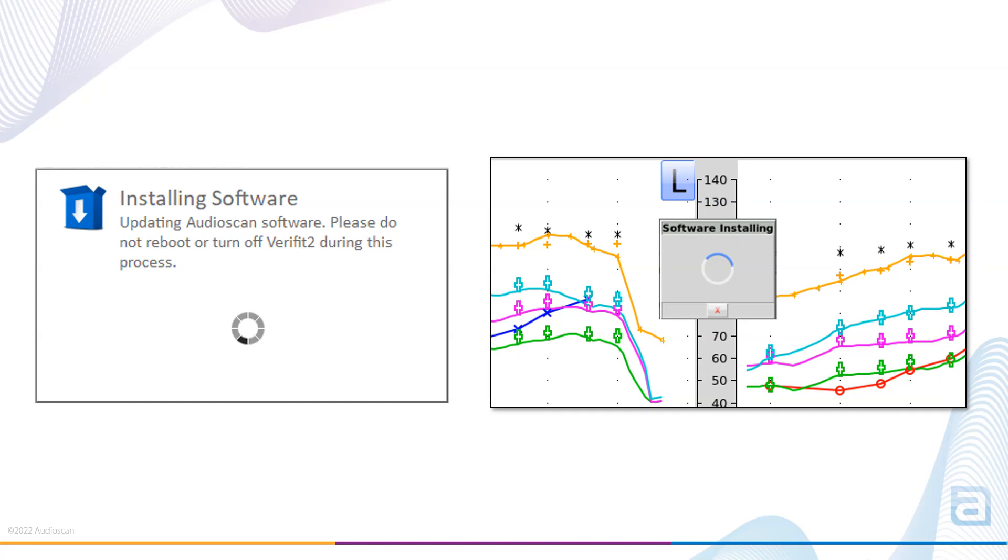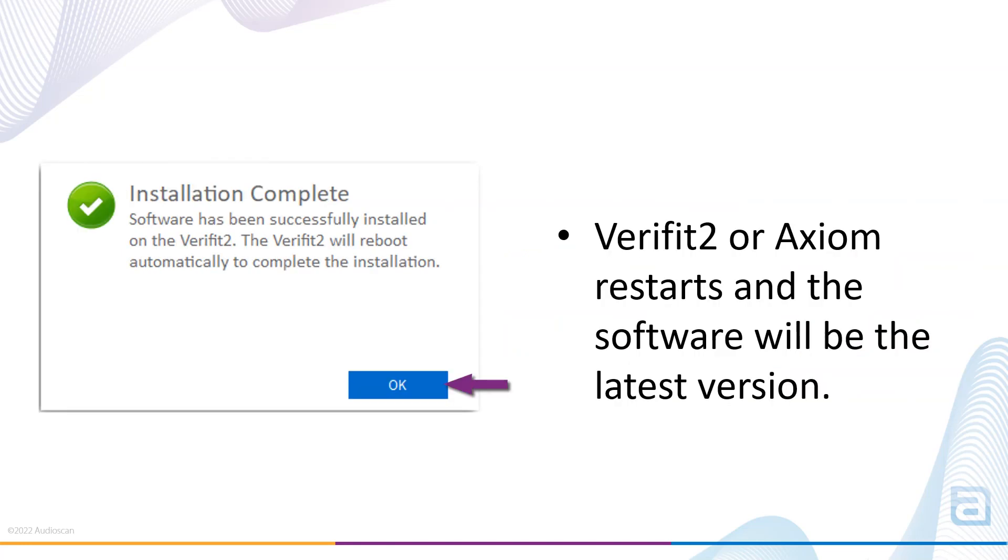If on the off chance you have a network issue or the equipment is turned off during installation and the update only partially completes, we recommend then using the Audioscan update USB stick to install the software update. Once the software update is finished installing on the equipment, an installation complete message will appear. The Verifit 2 or Axiom will restart automatically and reboot with the latest software version.